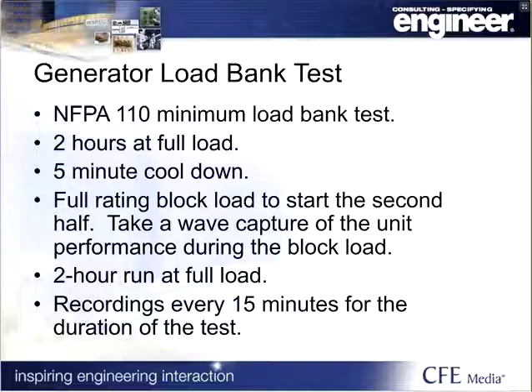A typical load bank test is 2 hours at full load, a 5-minute cool down, and then you're going to hit it with a full block of load of the generator rating. And you need to take a capture of that response and oil pressure and all the readings. Typically you're going to run it again for another 2 hours, and you're going to take recordings every 15 minutes throughout the whole duration of all 4 hours and 5 minutes of this. Now, there are other options. You can ask for a longer load bank test. I have done projects where clients wanted a load bank test, but then even tied it to load shedding to make sure that the system works appropriately, and whatnot.